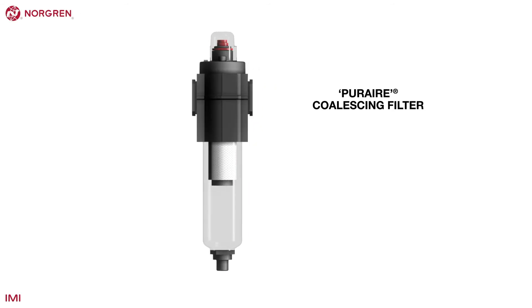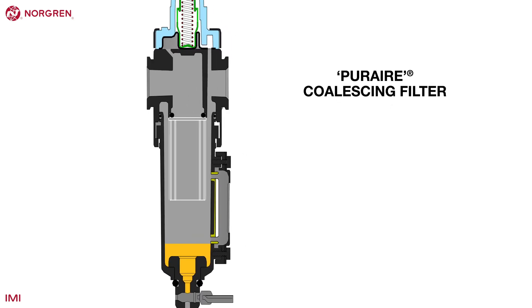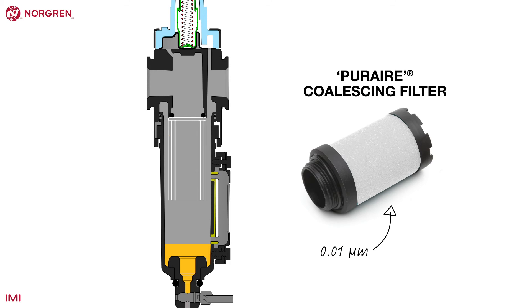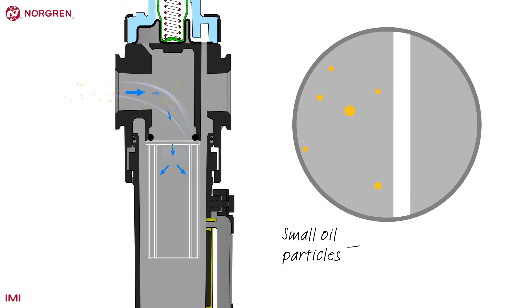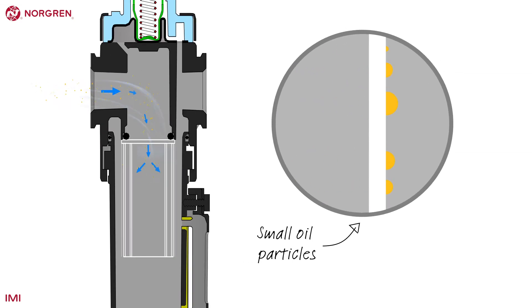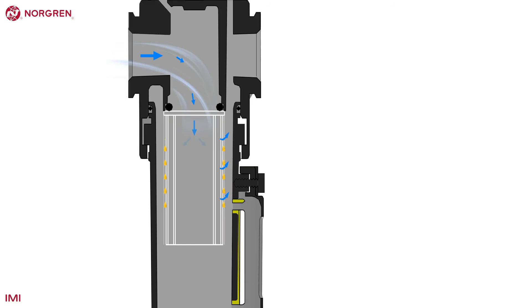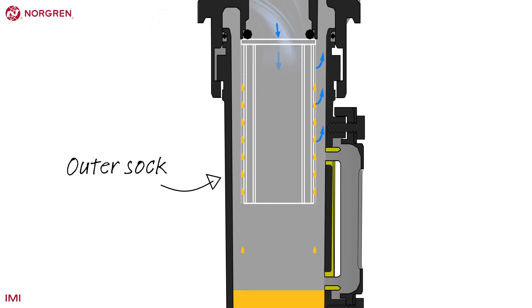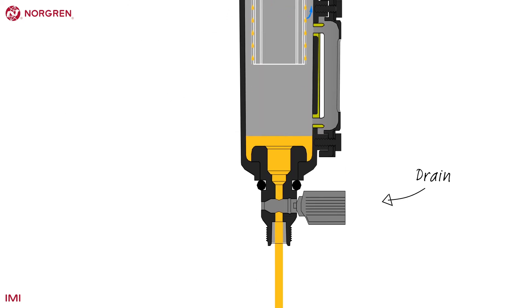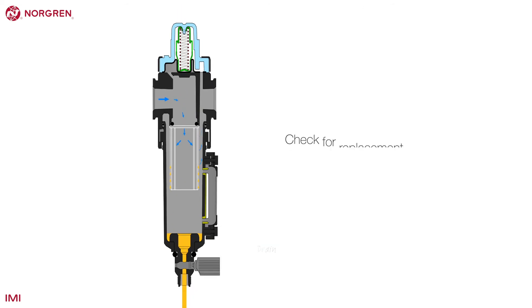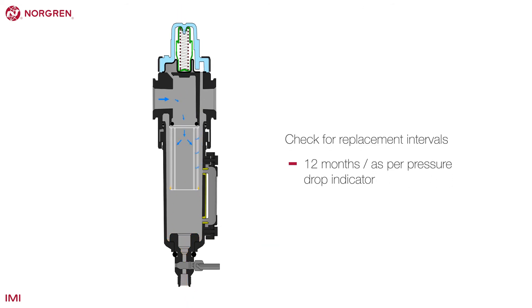Norgren's Puraire coalescing filter removes oil and extremely small particles down to 0.01 micron from compressed air. It works by forcing air through an element where it changes direction and bumps into itself, causing any oil to coalesce or stick together, creating bigger drops on an outer sock. As it gathers, it gains mass and gravity forces it downward into the bowl. You will notice a wet band around the sock as the oil gathers and drains into the bowl. Contaminant oil needs to be drained before it reaches the bottom of the element or it will be pulled back into the system. Check for replacement intervals and operating limitations regarding temperature.